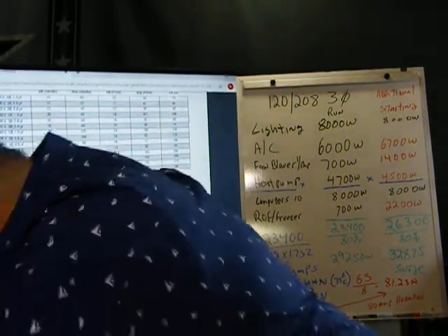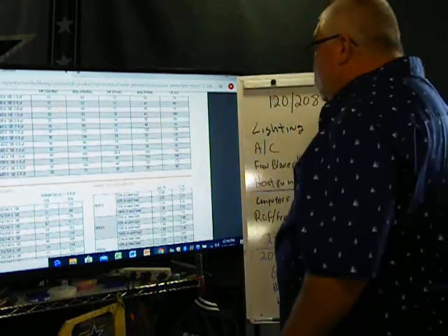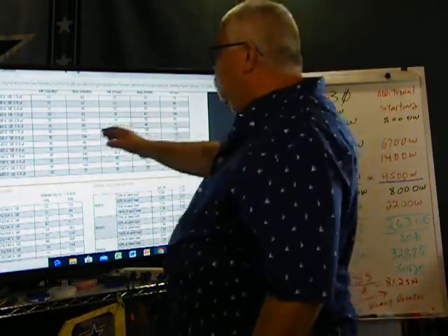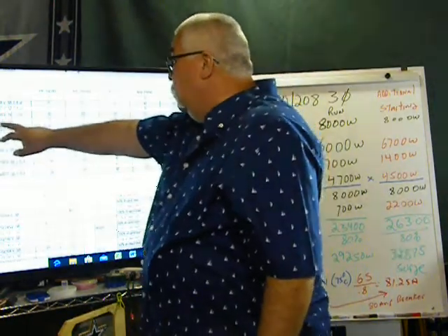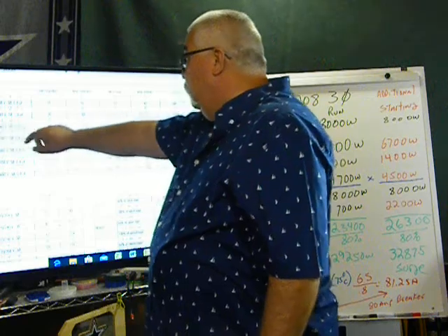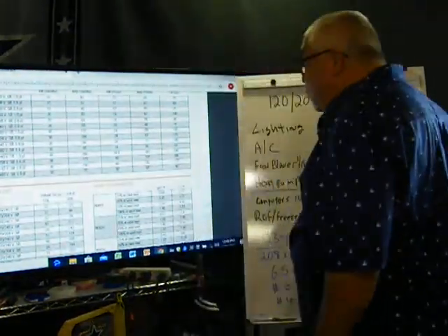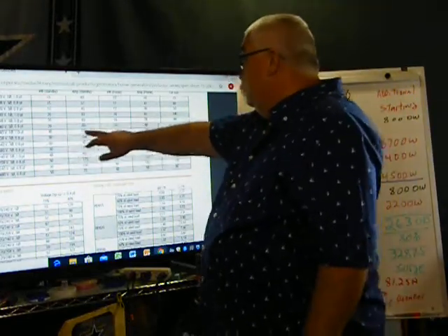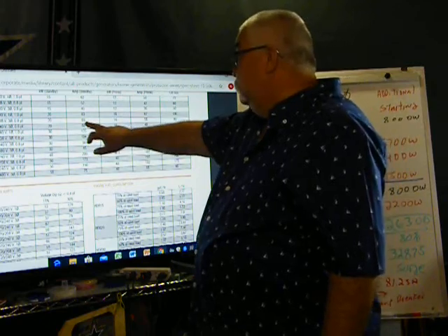So this is something I found, a PDF from Eaton. They're saying for the generator standby, a 20 kVA, 120/208 volts, 80% power factor, and that's what I added over here, that 80%. So it can do 69 amps standby.